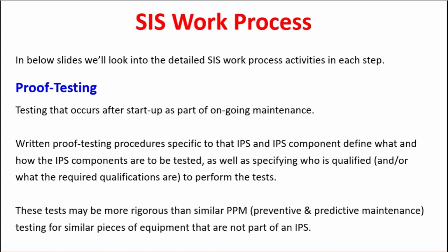If it is a 0 to 10 kg per centimeter pressure transmitter, the maintenance technician has to go and see that at minimum the sensor reading is zero when no pressure is applied, and when maximum pressure is applied, it has to measure the 10 kg per centimeter pressure.